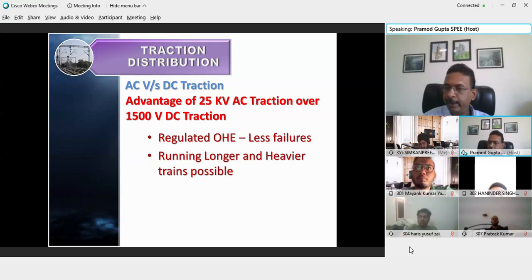If the sag is very high, the pantograph will also hit the OHE from the side, and it may damage either the pantograph strip or the contact wire. Therefore, we have an arrangement to control the overall tension maintained in the OHE, and such OHE is known as regulated OHE.